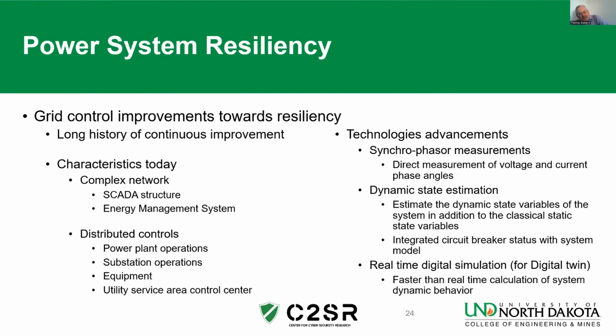And with dynamic state estimation, we basically start speeding up the time rates at which state estimation is being performed, give much better conditions of the state of our system, as well as modeling the dynamics of the system and coming up with the dynamic parameters, the dynamic state vectors for our system. This still is in the research areas where we haven't gotten this to a commercial state yet. But that's been an important goal for the industry. The other side of this is we've seen over time with better communications, the integrating of circuit breaker status with our state estimation so that we have much better modeling with better data coming in from the remote areas.